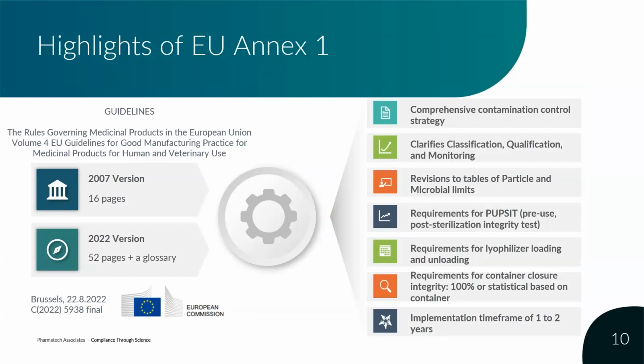Classification is referring primarily to the ISO standard, which is used to determine, for the EU, the grade level of the particular clean room. In the US, it uses the ISO class number. So that's specific to that ISO standard. Qualification is a more general term that not only includes the classification, but also such things as the HEPA integrity testing, the pressure differential measurements, the air changes, the face velocity, et cetera, that is used to essentially qualify the clean room, and in fact is used now within the annex to re-qualify the clean room on a periodic basis.